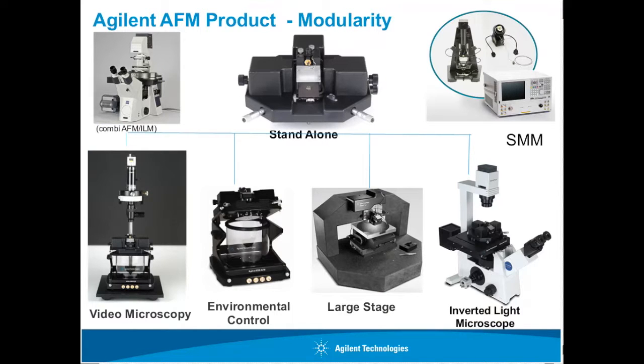We have several AFMs that can be used for this scanning microwave microscope. Here you see an overview of our Agilent product modularity, ranging from simple AFMs to more complex AFMs. For instance, the large stage AFM has very low damping so mechanical noise is low and you get very good resolution topographical images. On the upper right, you see the SMM sketch showing a simple AFM with a network analyzer, which I'll come to in more detail.